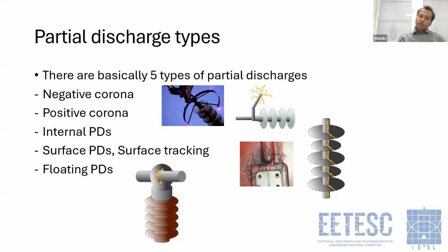Okay, when it comes to internal PDs, as I said earlier, internal PDs can happen internally, for example inside a transformer or GIS, as well as inside an insulator. As an example, if there is a void inside an insulator, the field in that void might exceed the breakdown voltage, so a partial discharge can happen. Usually those partial discharges cannot be detected with these acoustic cameras, but both negative corona and positive corona can be easily detected with these acoustic cameras.